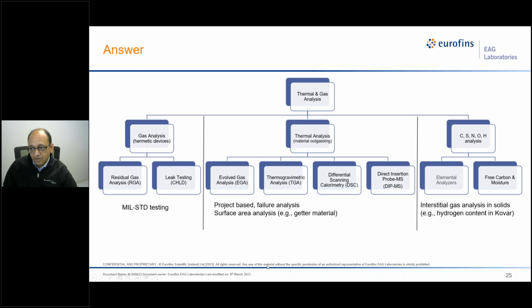And then we have a separate department with a long list of instrumentation available for thermal outgassing. So we use this for a lot of failure analysis, as well as when we want to understand the thermal stability of a part, or powder, or any kind of ceramic, or even the getter material or the epoxy being used as an adhesive. All can be tested in this department by using a variety of methods like evolved gas analysis. We did a webinar on this, and there is good information on this particular technique. We also have TGA and DSC methods, as well as a direct insertion probe method. We have also recently added a method where we can analyze the surface area for the powder.